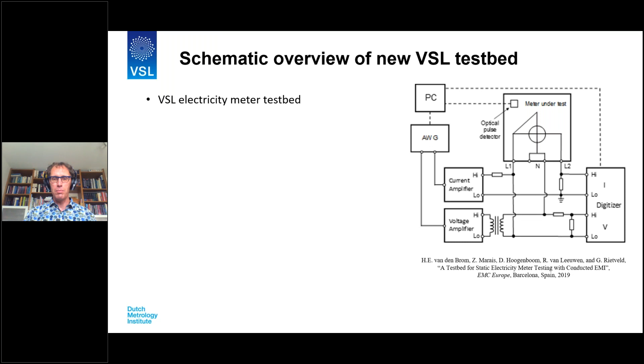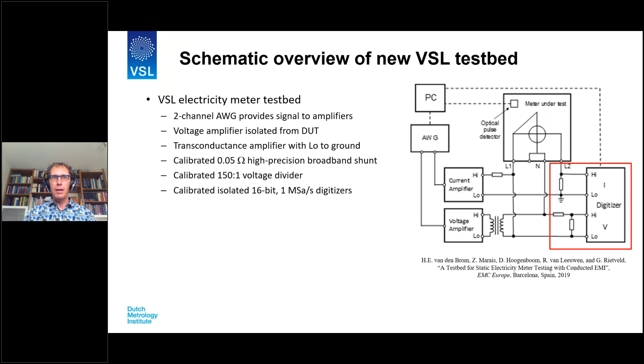The test signals are applied through an arbitrary waveform generator with a voltage amplifier and a transconductance amplifier. The current is then measured through a broadband precision shunt, and the voltage is measured through a broadband resistive divider. The data are sampled with 1 megasample per second, such that we at least capture frequencies sufficiently high. Then an optical sensor is used to register the energy reading of the meter under test. And the meter error is then determined as the relative difference between the meter reading and the reference setup.